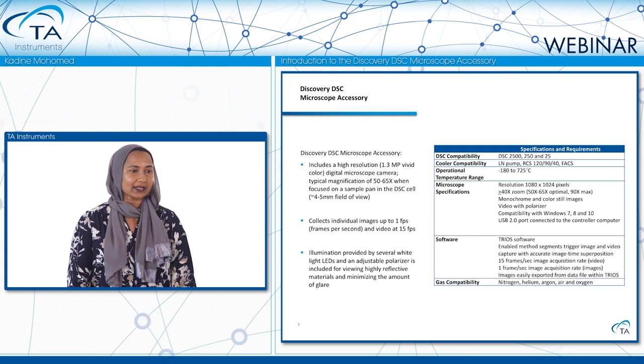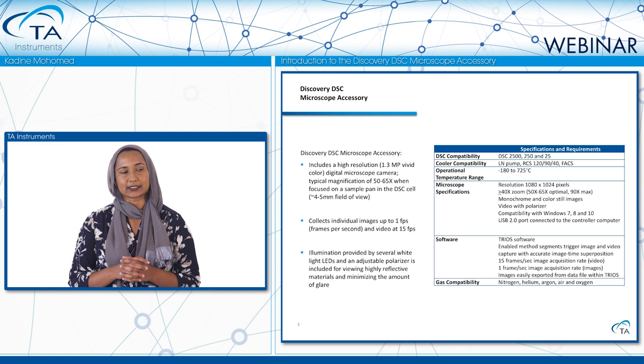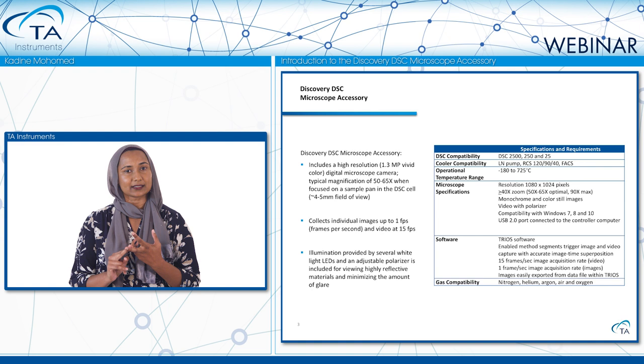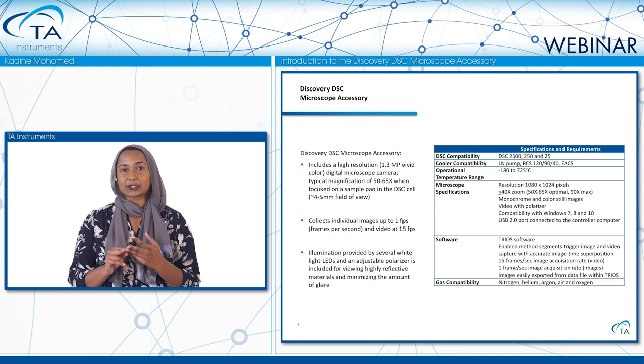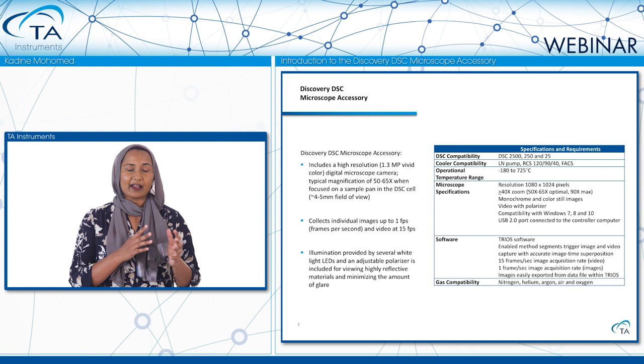The camera is compatible with the DSC 2500, 250, and 25, as well as a wide range of cooling accessories: the LN pump, all of the refrigerated cooling systems — the RCS 120, 90, and 40 — and the FACS cooler. That gives you an operational temperature range, depending on the cooling accessory installed, of minus 180 degrees all the way up to 725 degrees Celsius.